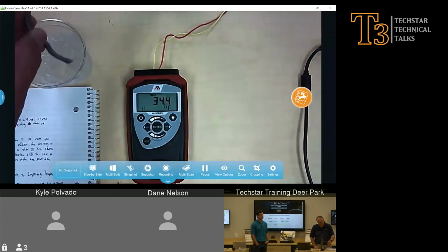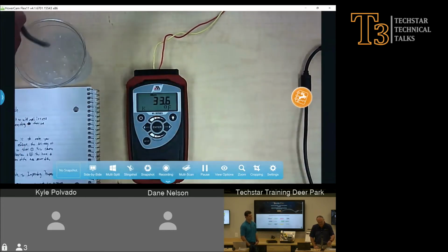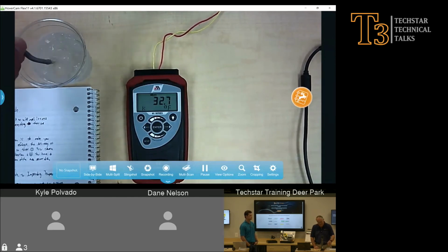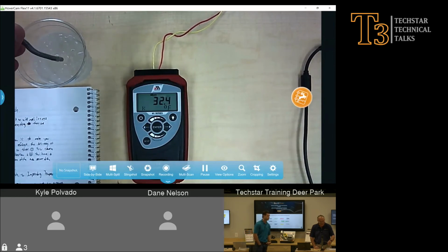If I had just taken this directly, oh, whoops. There you go. Okay, so it's already at 33. So we're in pretty good shape because we were saying it's a 4-degree device, and already we're well within range. To give you some idea of the response, one way to do it is just do an ice bath.